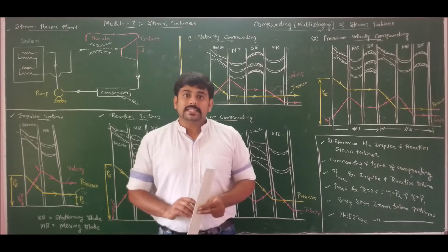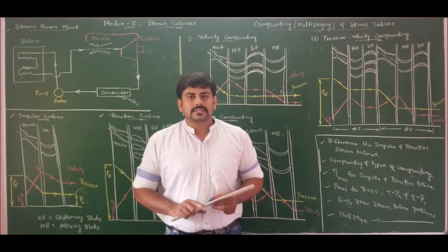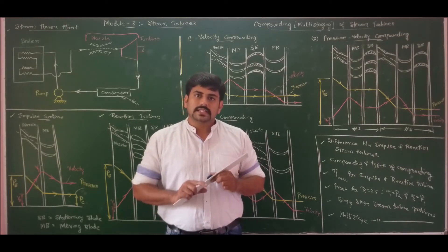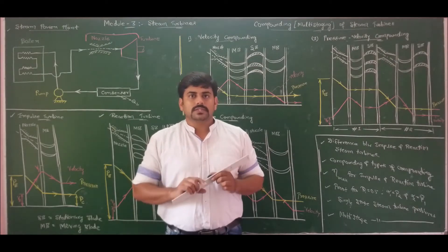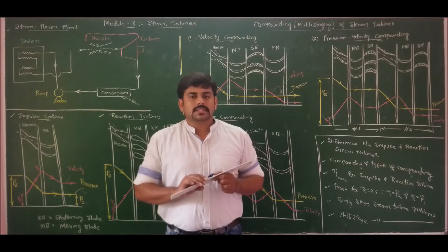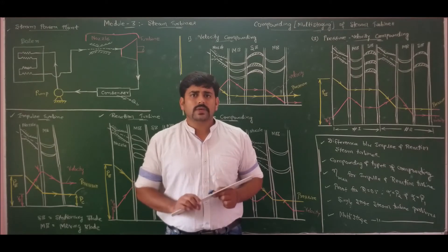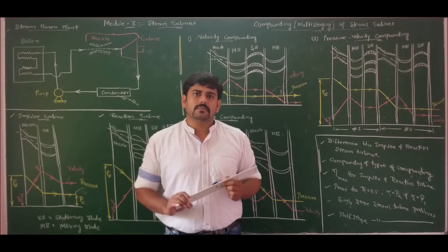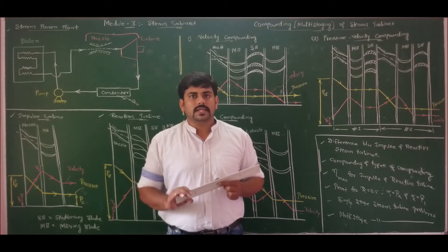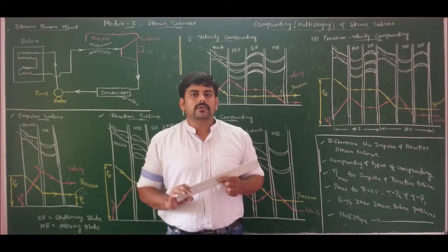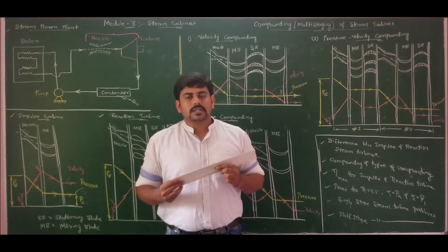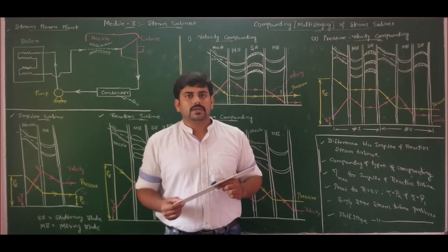Compounding is nothing but multi-staging. Compounding is necessary in steam turbines because the discharge velocity V2 is high, making utilization less for a single stage. For maximum utilization, V2 should be minimum — V2 is minimum when it equals the flow velocity Vf, meaning the discharge velocity of steam is purely axial. To maximize utilization of the kinetic energy present in the steam, we use multi-stages or compounding.